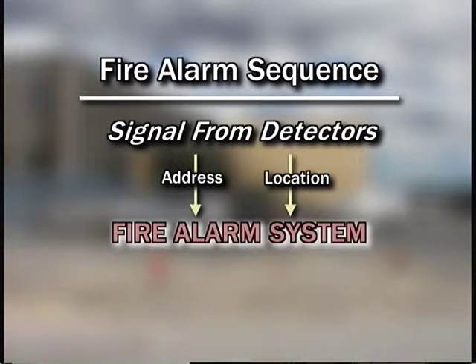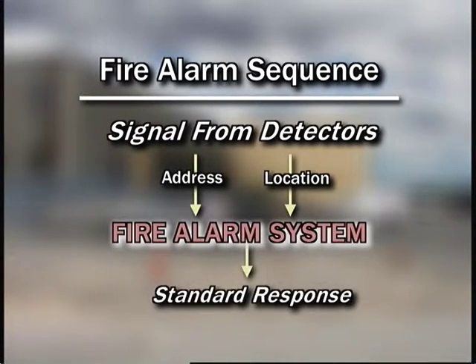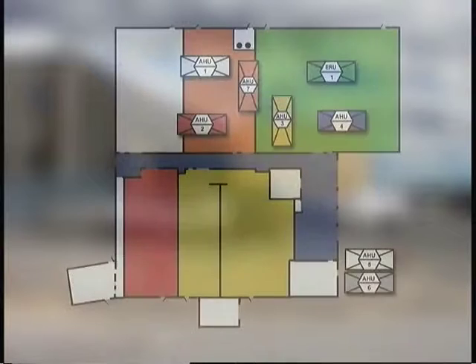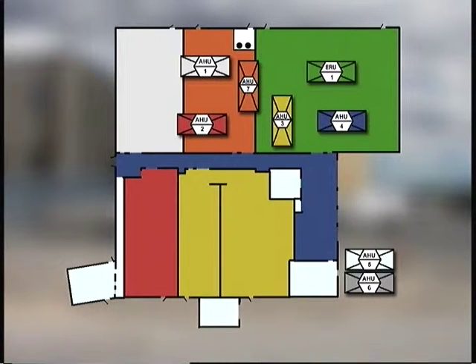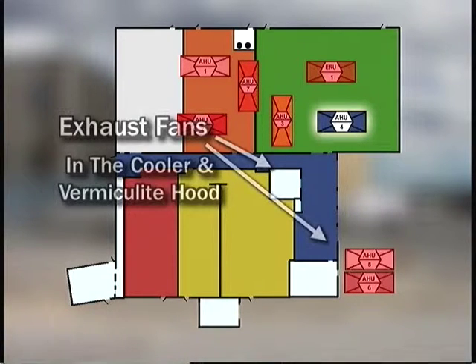Associated device and its location to the fire alarm system, which, in turn, will trigger the standard response that includes activation of horn strobe devices throughout the facility. All air handling units, including AHU 1, 2, 3, 5, 6, and 7, as well as ERU 1, will be signaled to shut down. The exhaust fans for the cooler and the vermiculite hood will shut down.